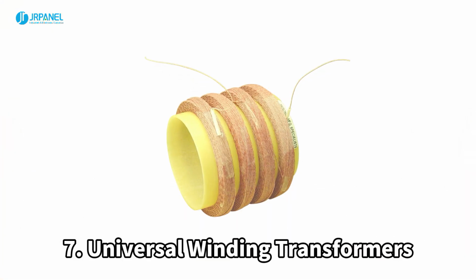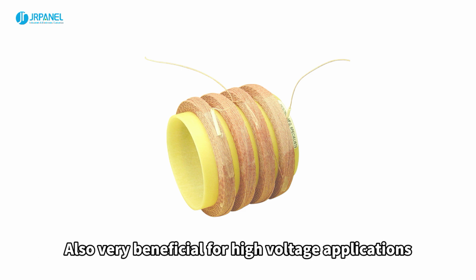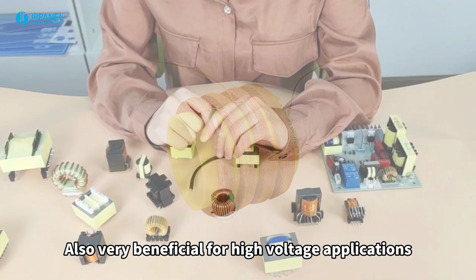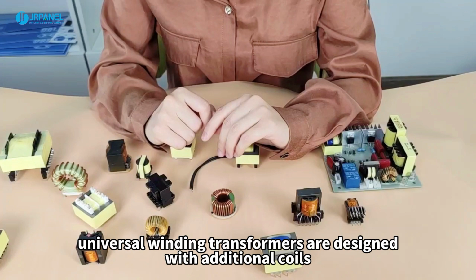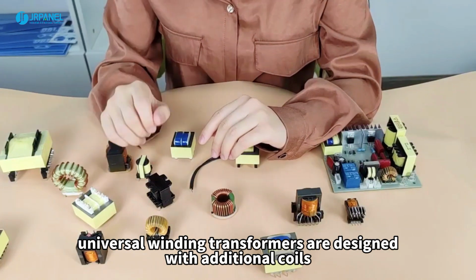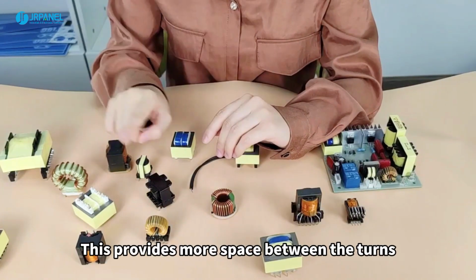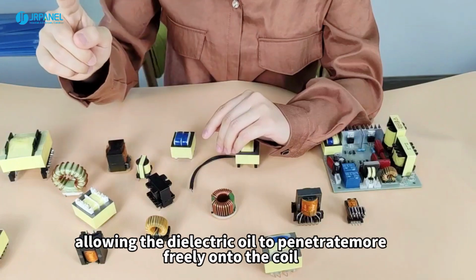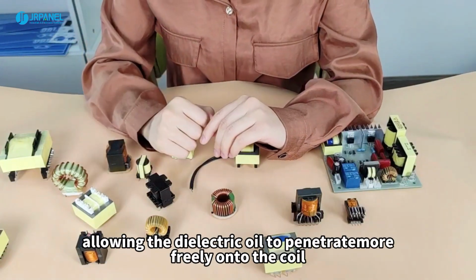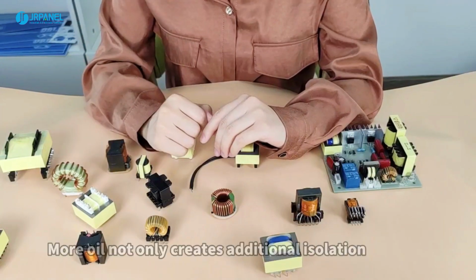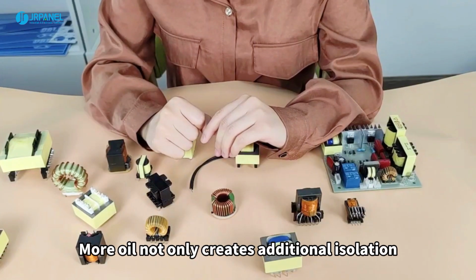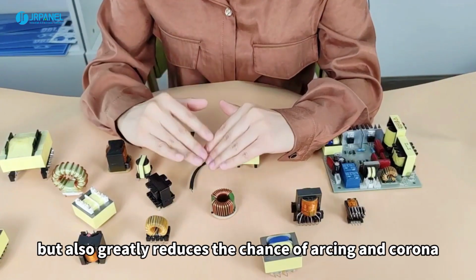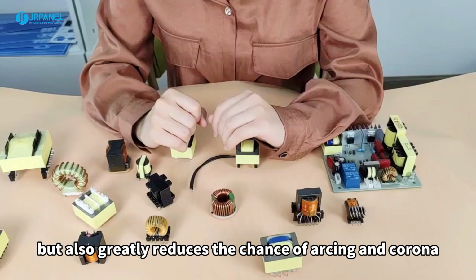Universal winding transformers, also very beneficial for high voltage applications, are designed with additional coils. This provides more space between the turns, allowing the dielectric oil to penetrate freely onto the coil. More oil not only creates additional isolation, but also greatly reduces the chance of arcing and corona.